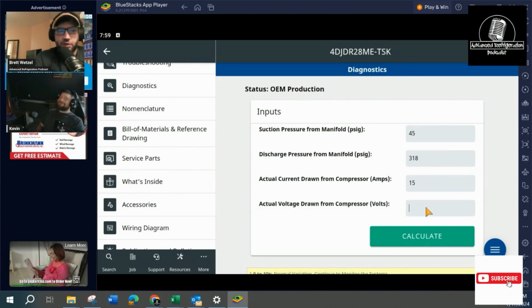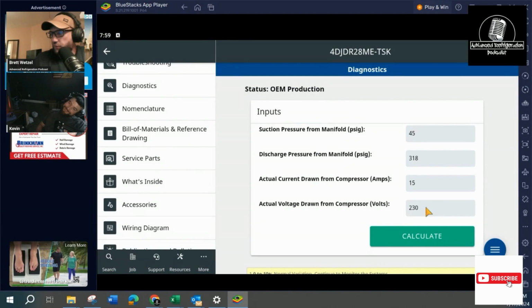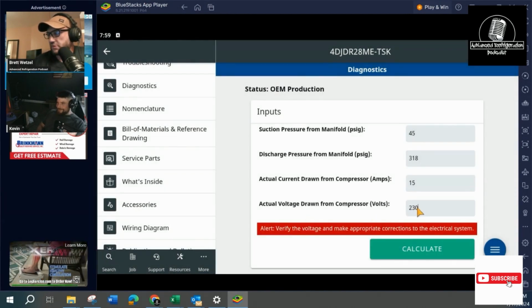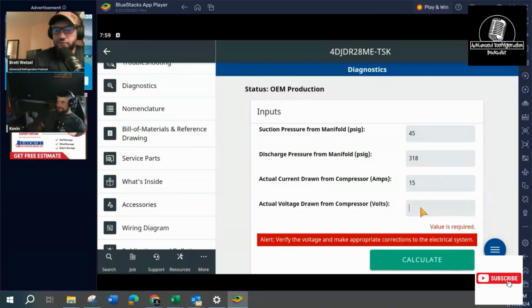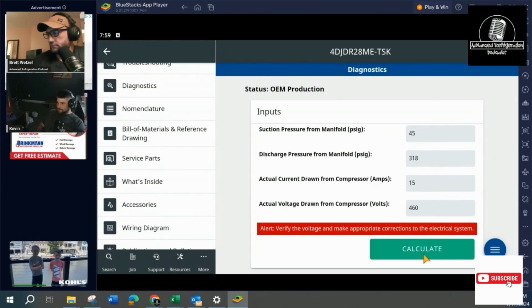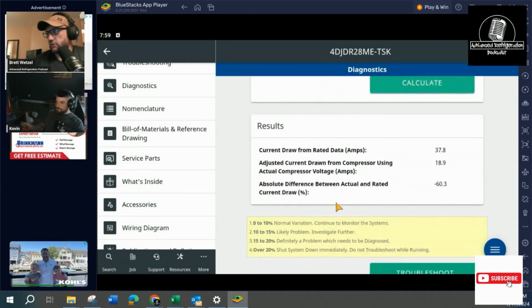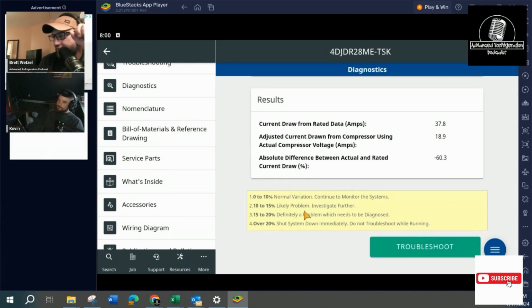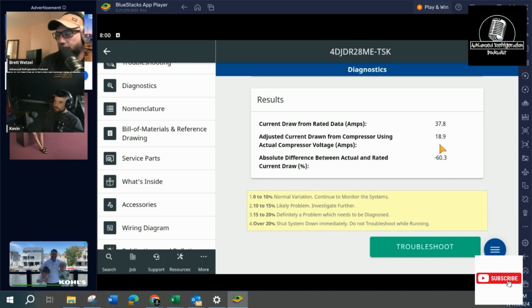I should have taken a screenshot. Oh my God, this is awesome. Let's just keep it rolling. Calculate. Nope, it's 460. Yeah, it definitely was a 460 then. Okay. Now, based on the current draw rated 37.8 amps, adjusted current drawn at the compressor using the actual compressor voltage 18.9, absolute difference between the actual and rated is negative 60.3. And it tells you that if it's 10% off, that's normal. If it's 10 to 15, likely a problem. 15 to 20, definitely a problem. Over 20%, shut that down. It's totally broken. We're at the shut it down, totally broken stage.